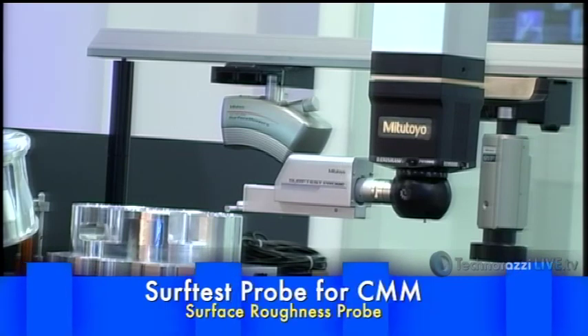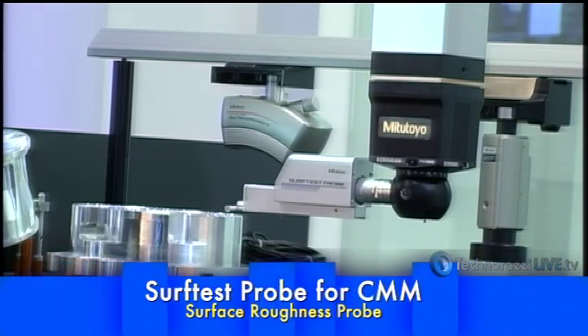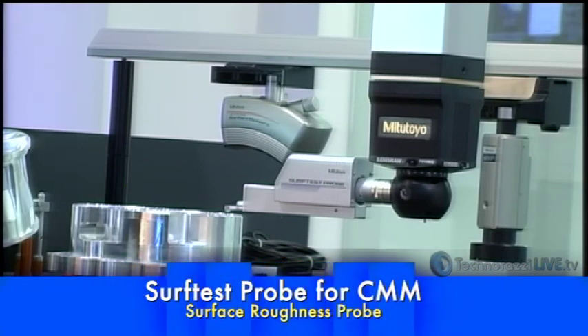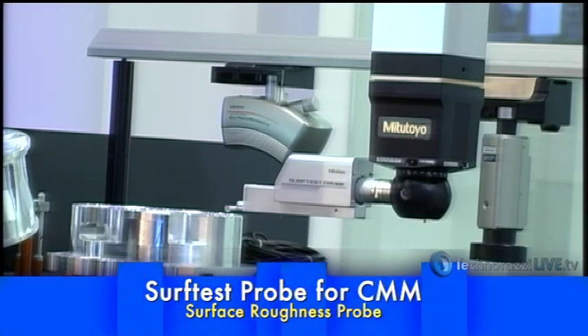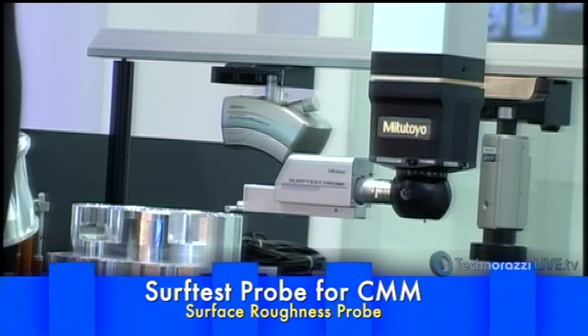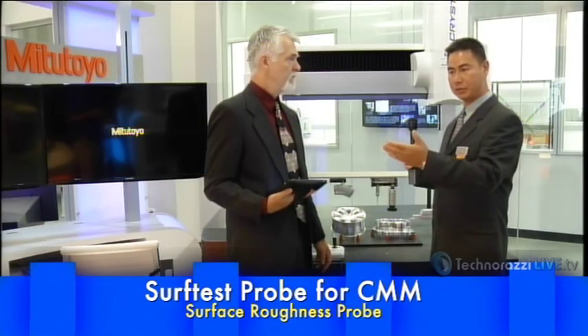Okay, now one thing I'm interested in is, since this is on a CMM, are you able to correlate that surface roughness measurement with a particular location on a part? Say maybe you've gone around the part, you've scanned it, or you've touch probed it. Now you go back in, you pick up your surf test, you make a measurement. So now on the results, you're able to correlate that surface roughness measurement with a specific spot on the part? Correct. You're able to go back to the exact spot and look at the surface analysis of that area through the two softwares that we combine, MCOSMOS and FormTracePak.